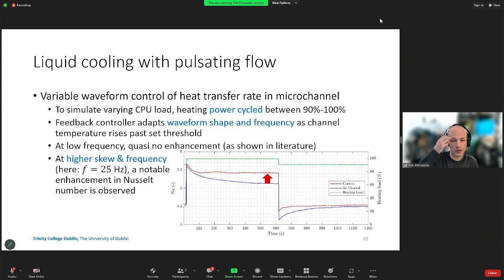So what you see over here is what happens if the power cycles between 90% and 100%, which is the green line over here. And the response without a control is that the apparent Nusselt number will change, of course, because of the thermal inertia in the system. But then as we enable our control, and this is done for this case over here for a frequency of 25 hertz, we're effectively going from a steady flow to a pulsating flow. We can see that we have effectively an enhancement of the Nusselt number.